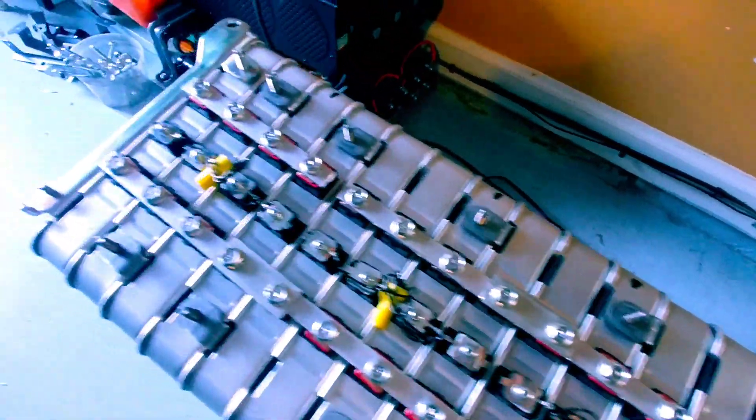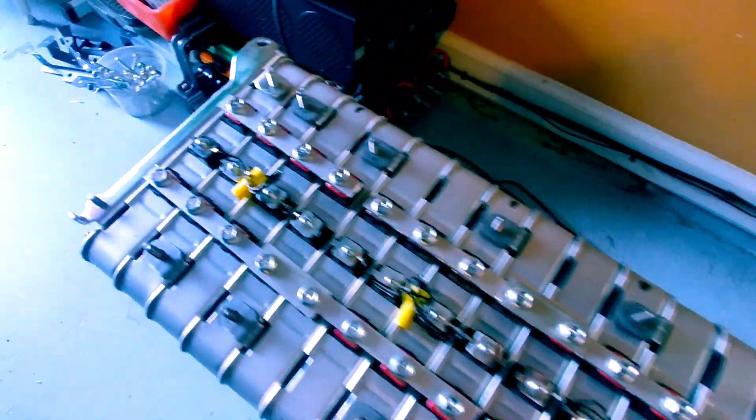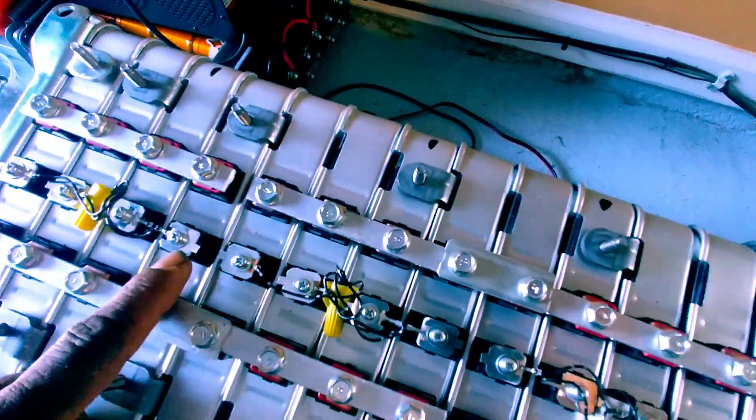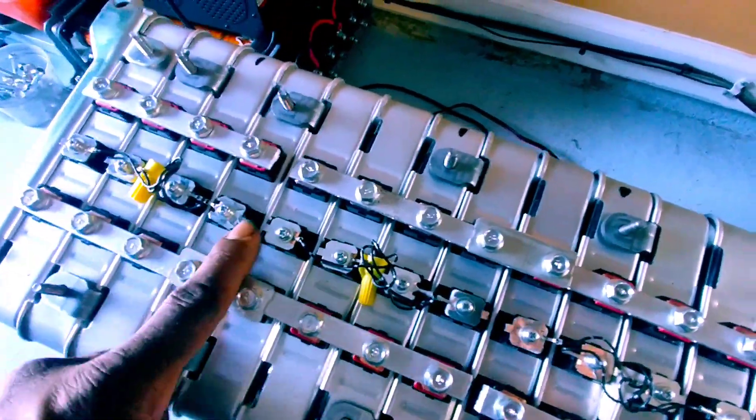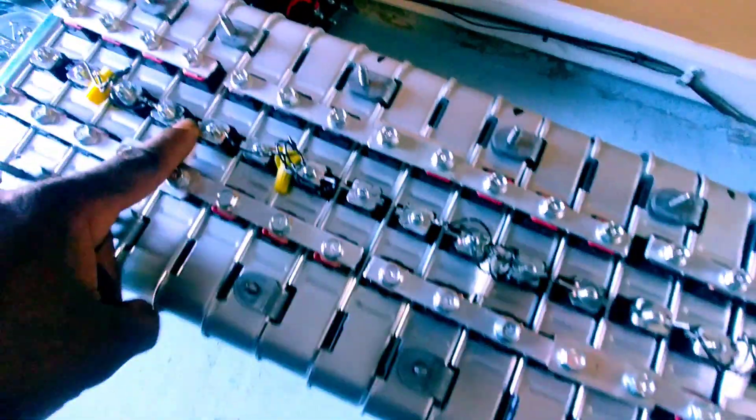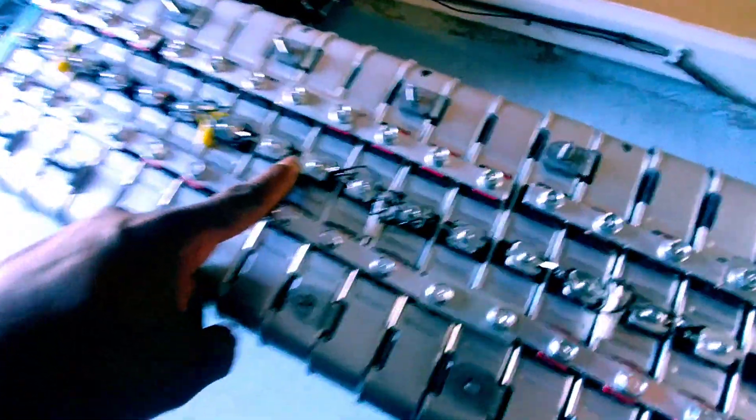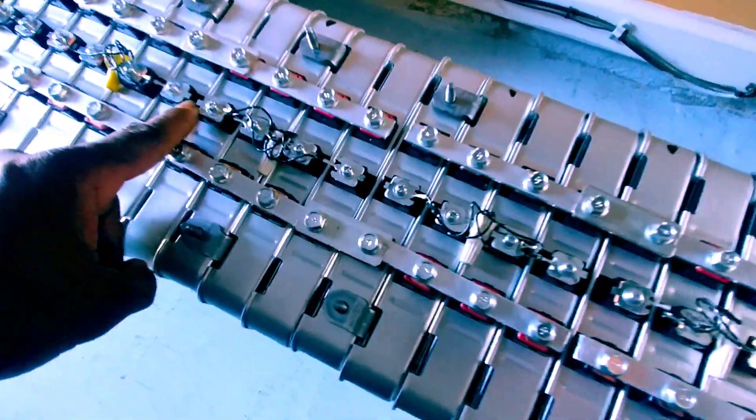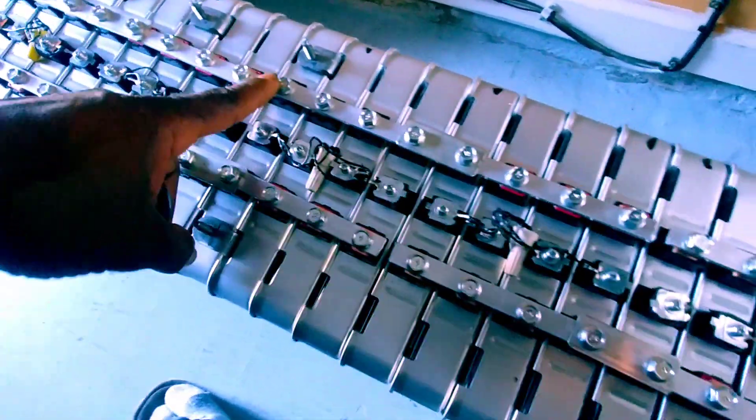So this is one big 48 volt bank. And same thing with the center. Four on top, there's a space. Four on top, space. Four on top, then it's a space. All the way down.